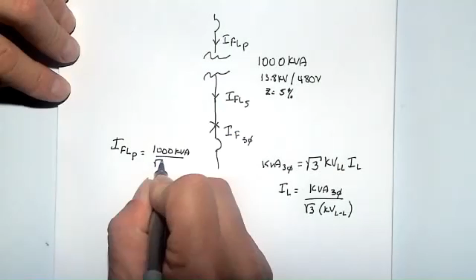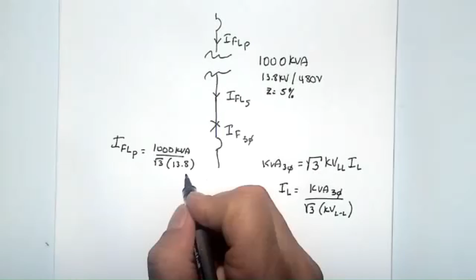So for example, current I full load on the primary is 1000 kVA divided by the square root of 3 divided by 13.8 kV. And so let's calculate that out. 1000 kVA divided by 1.73 divided by 13.8. And that works out to be about 42 amps. Okay. Now, if we want to look at the secondary current, I full load secondary, we would take 1000 kVA divided by the square root of 3 divided by 480, right?